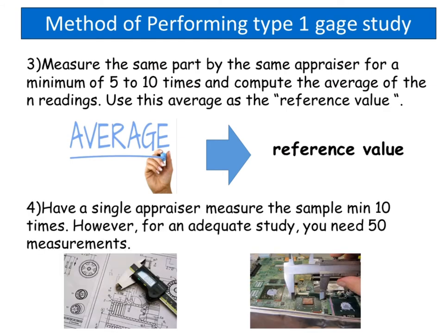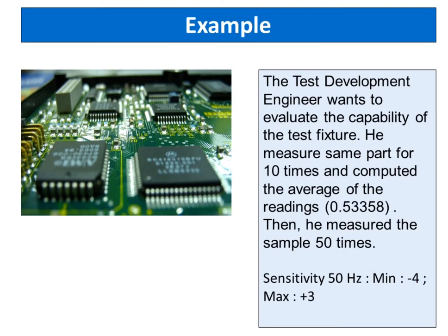Have a single appraiser measure the sample a minimum of 10 times. However, for an adequate study, you need 50 measurements. For example, a test development engineer wants to evaluate the capability of a test fixture. He measured the same part 10 times and computed the average of the readings: 0.53358. Then he measured the sample 50 times.